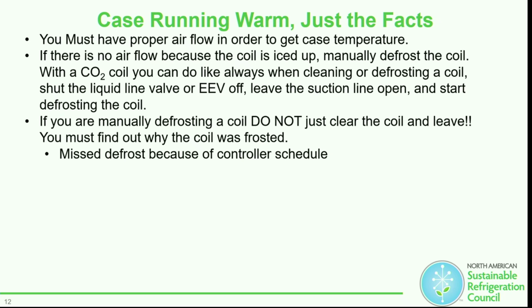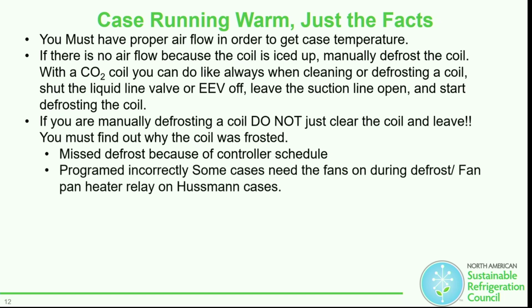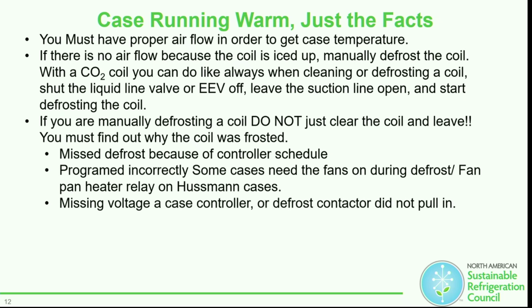But yes, we need to find out why. Missed defrost because of a controller schedule programmed incorrectly. Sometimes cases need the fans on during defrost. You know, the fan pan relay heater that we were talking about. Missing voltage to a case controller could be low voltage too. If that voltage is being designated to go into a defrost and maybe it's losing communication, it might miss a defrost because of a low voltage situation for the supply of that case controller.